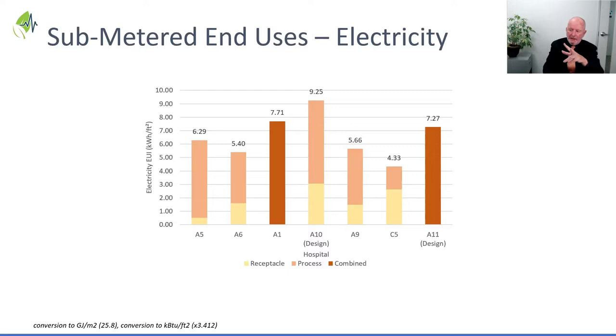In a couple of cases, these are all merged together. They weren't able to provide separate numbers. But once again, you'll see A10 would seem to be significantly overestimating the internal heat gains there. And this again is modeling results. A10 almost certainly then relates to why the chiller energy is too high and the pumping energy is too high, because most of the people on this call know how that works. If you overestimate internal heat gains, you missize and incorrectly estimate everything going with that.